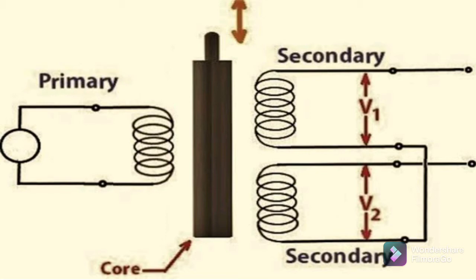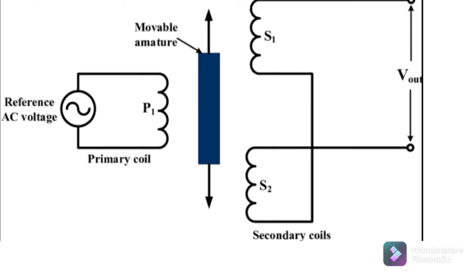As shown in the figure, hydrogen annealing is done on the core to reduce the harmonic residual voltage from the core and thus provide high sensitivity. The movable core is also laminated in order to reduce the eddy current losses. The displacement to be measured is attached to this movable soft iron core. LVDT is placed inside a stainless steel housing because it provides electrostatic and electromagnetic shielding.